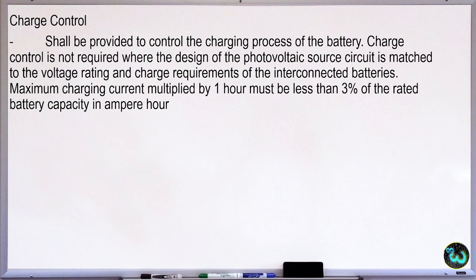So a charge controller shall be provided to control the charging process of the battery. Charge control is not required where the design of the photovoltaic source circuit is matched to the voltage rating and the charge requirement of the interconnected battery. So if the charge voltage of the PV panel and that of the battery match, a charge controller is not required. But the usual case is there is no real match, because the voltage output of a panel will fluctuate depending on the light output of the sun.